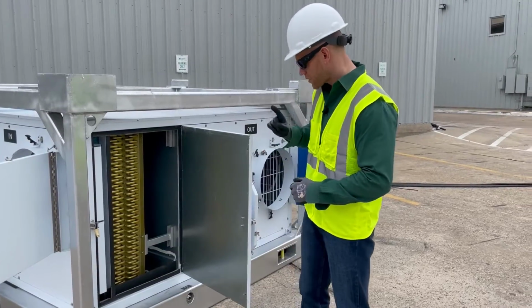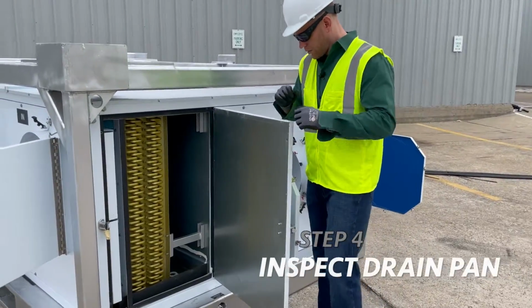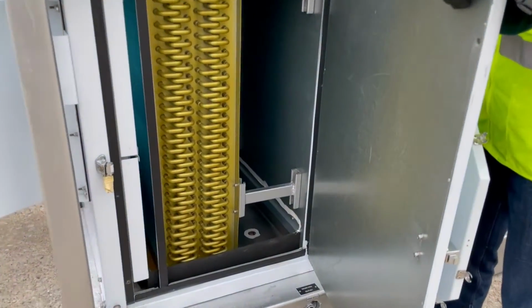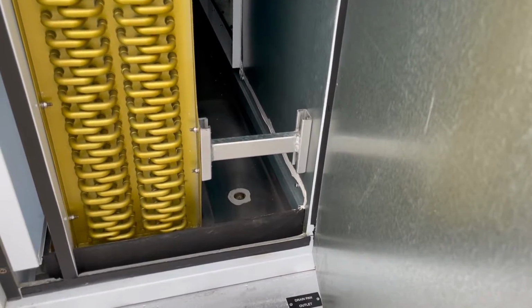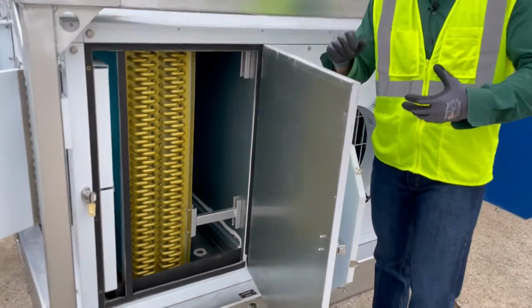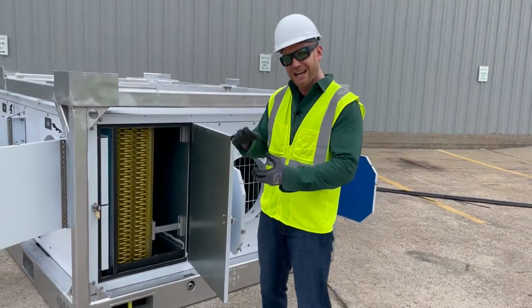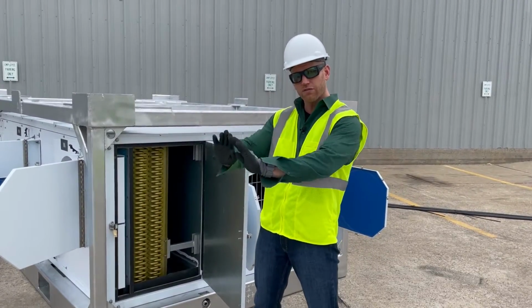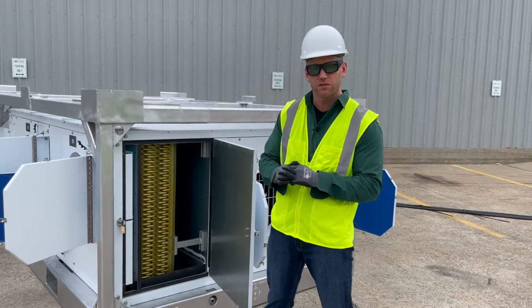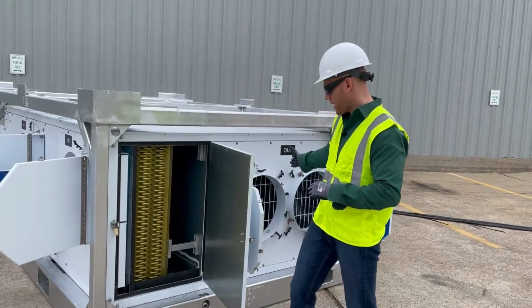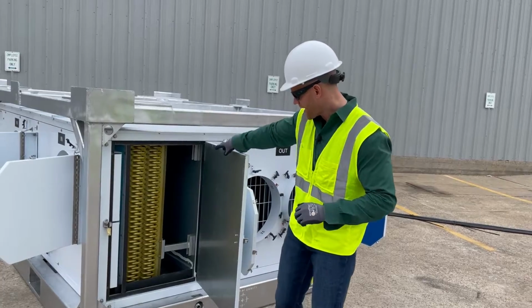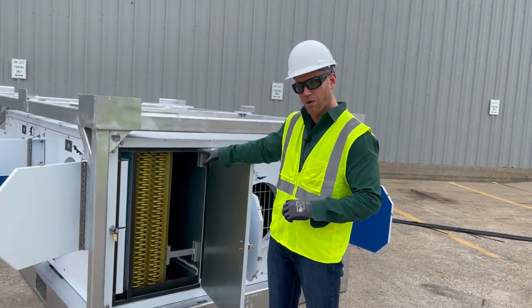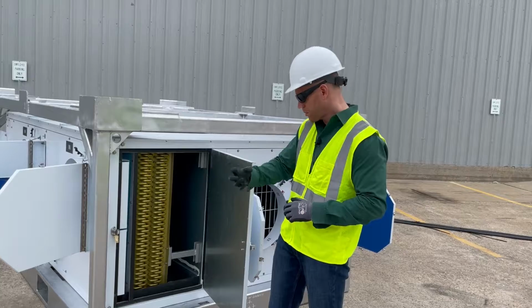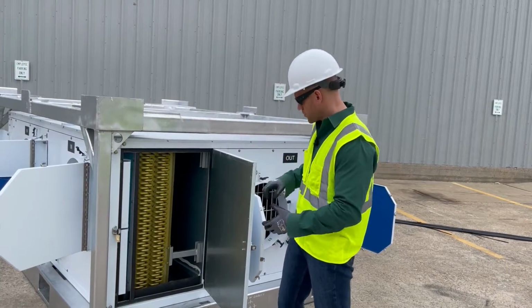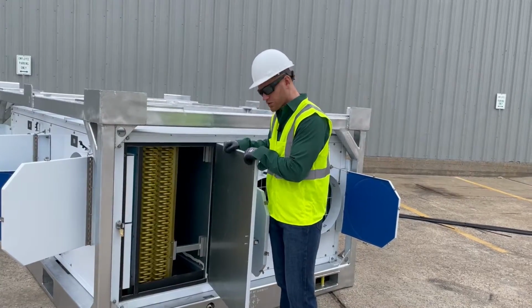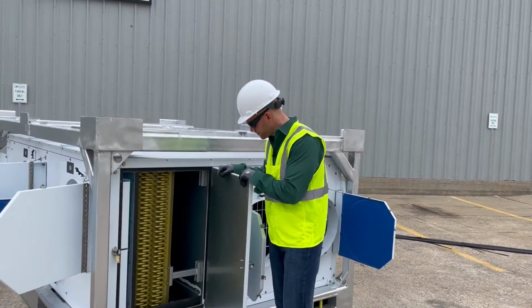Step 4, we want to inspect our drain pan. So if we come in and we look inside, we see that our stainless steel drain pan is very, very nice, clean, nothing's in there. I said in the beginning of this video that this is a high static model. We can generate a lot of force behind the air that we're going to be delivering to the job site. Well, because we have a lot of positive pressure, positive force here, we're going to have a lot of suction on the inlet side of the blower. So we never want to leave anything in that drain pan that could get sucked in there. Sometimes people will leave things in here, so as a standard we always go in and check and make sure the drain pan is clean.